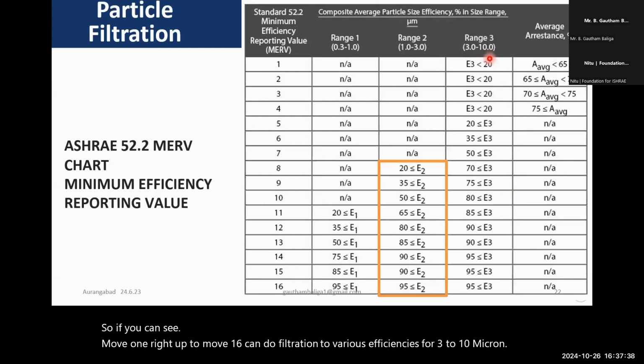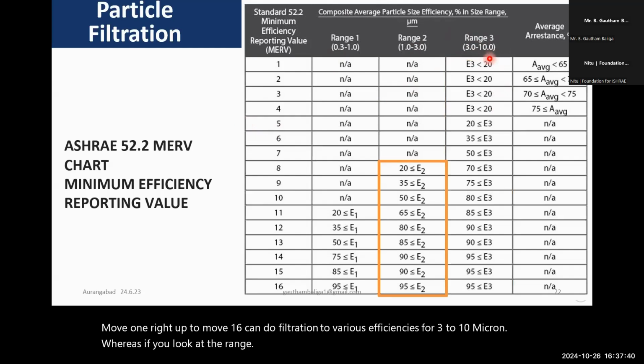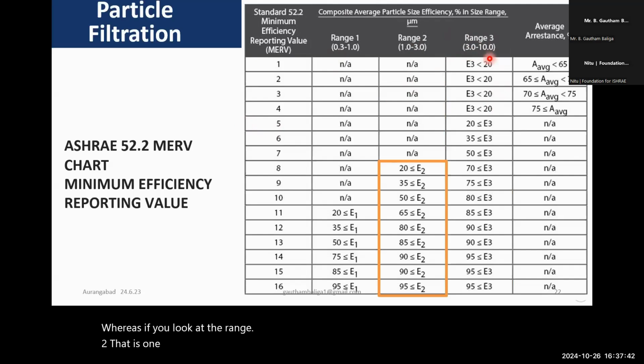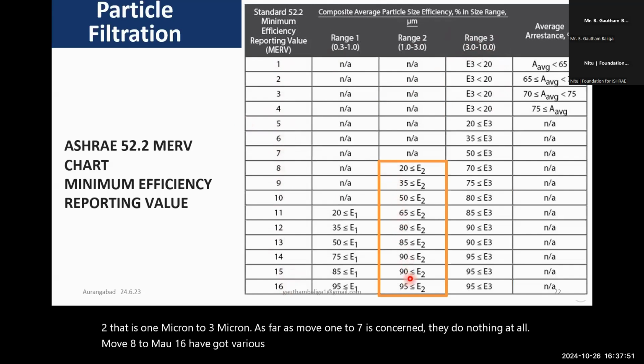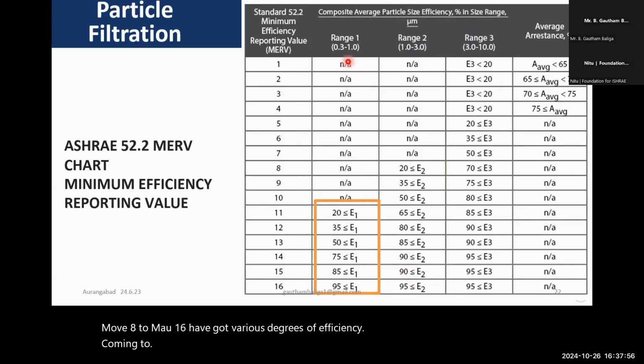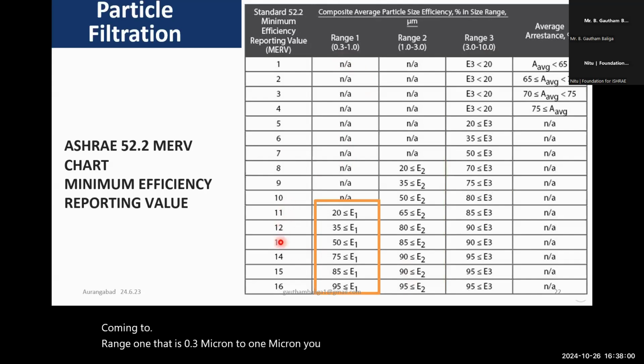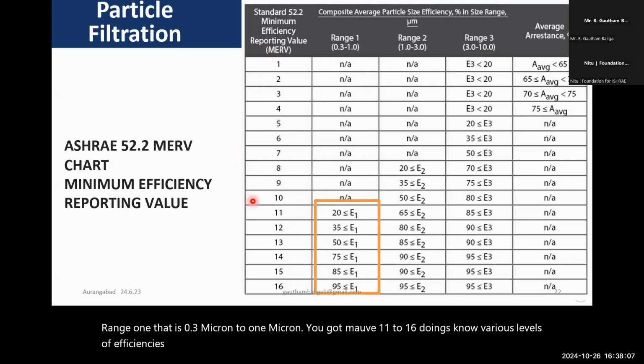Whereas if you look at the range 2, that is 1 micron to 3 micron, as far as MERV 1 to 7 is concerned, they do nothing at all. MERV 8 to MERV 16 have got various degrees of efficiency. Coming to range 1, that is 0.3 micron to 1 micron, you've got MERV 11 to 16 doing various levels of efficiencies, whereas MERV 1 to 10 don't do anything at all.